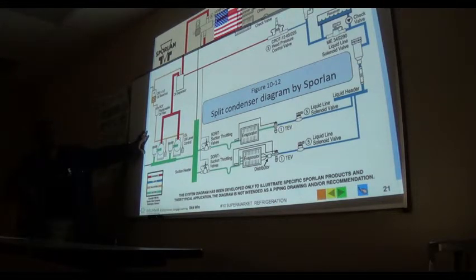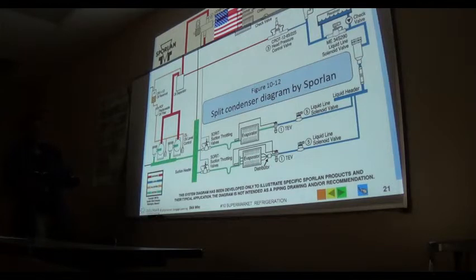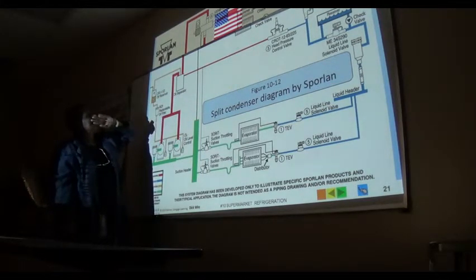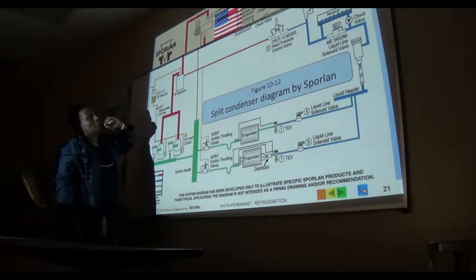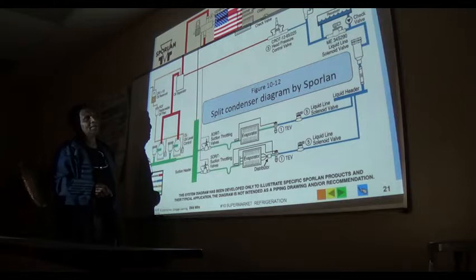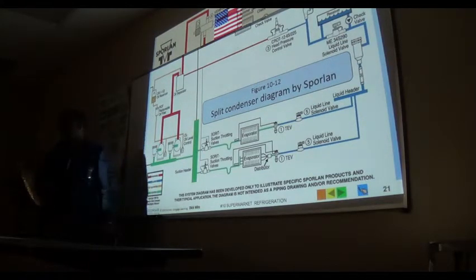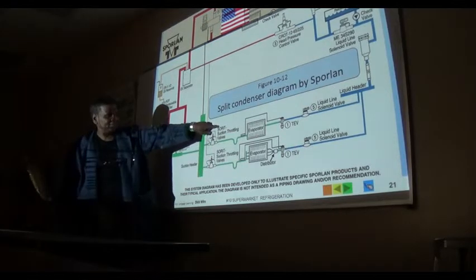So, this is... let me see the legend on this. Why do you have only two compressors? All right. Suction manifold, discharge manifold, oil separator. Pressure control valve. Two of them, yes, and see that CROT? It means closes on rise of outdoor temperature. Right, because as the temperature rises, you want the gas to go through the... The other one is open on rise of indoor temperature? Yes, because it's under suction. Okay. And the S means it is under suction, right? Yeah.